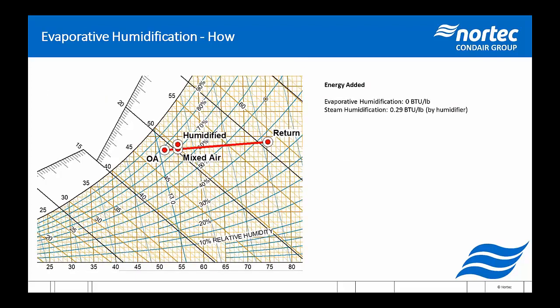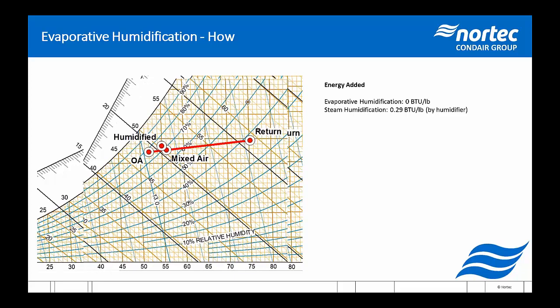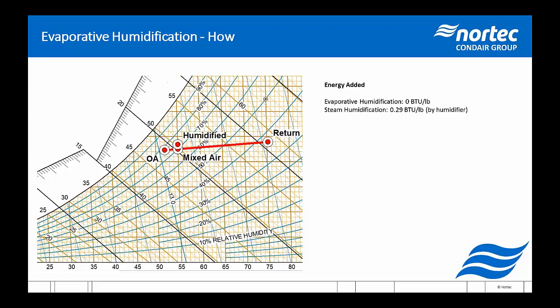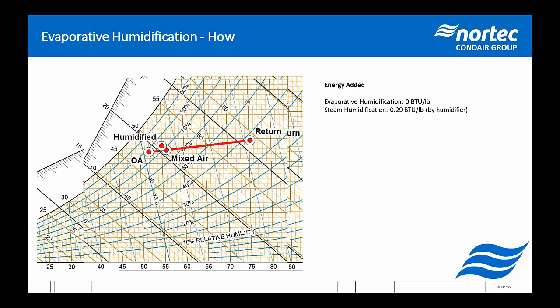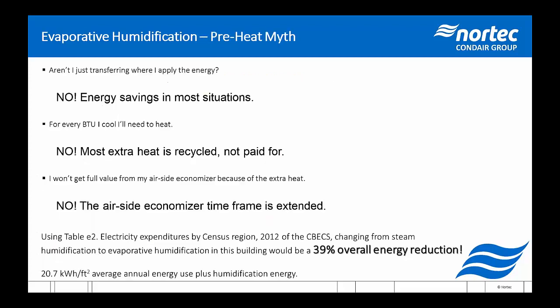And finally, we've got one of these situations where the difference is basically negligible. The outside air is cool, but cooler than our set point, so we're able to mix to our set point. An evaporative humidifier is putting in effectively 0 BTUs per pound, whereas a steam humidifier is putting in 0.3 BTUs per pound to maintain your set point. I go back and forth on that a few times.